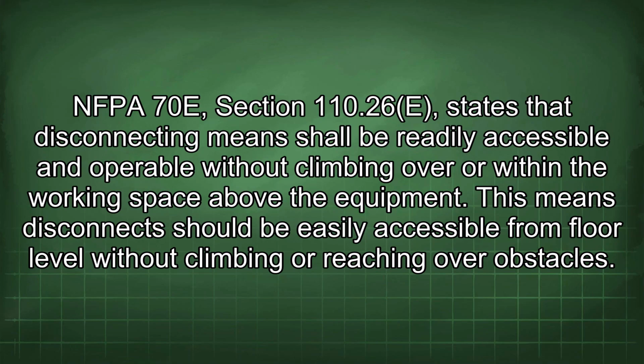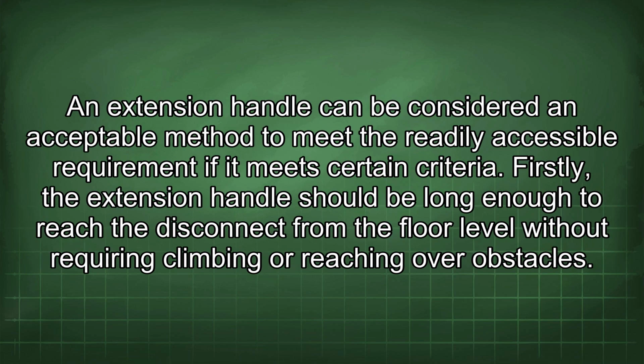NFPA 70E, Section 110.26(E), states that disconnecting means shall be readily accessible and operable without climbing over or within the working space above the equipment. This means a disconnect should be easily accessible from floor level without climbing or reaching over obstacles. An extension handle can be considered an acceptable method to meet the readily accessible requirement if it meets certain criteria.